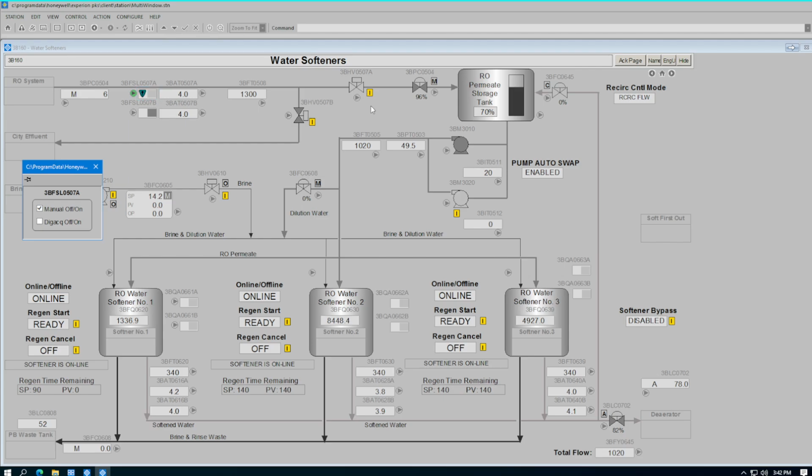After a confirmed close of valve A, this pressure control valve will go into manual mode and hold its last position. We must correct the situation that created the alarm before we can return to normal operating positions. And this does not switch back automatically by design. The operator has to confirm that we have good conductivity, and then you can open valve A.